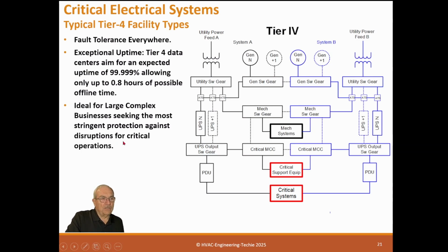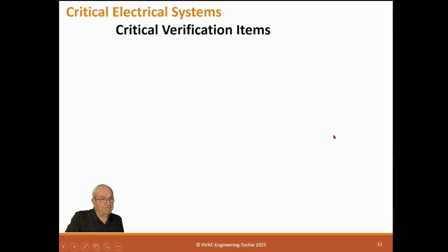So this is a Tier 4 system, which is the top one. And you can see the mechanicals are N+1, and the support is also N+1. So not only do we have the whole inside, but we have N+1 everywhere, totally fault tolerant. That's an exceptional system.